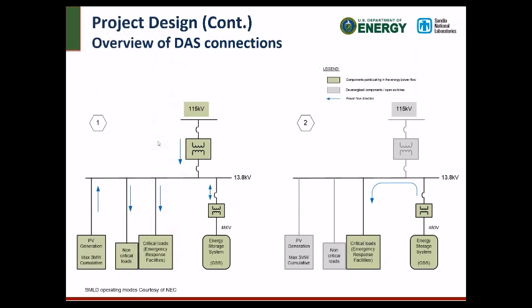So as you see on the screen now, on the left side we have a normally operating system. The green means it is on, and the arrows show the power flow. We have energy storage on the right and PV generation on the left, with critical loads and non-critical loads between. On the right side, if we had a utility outage, the battery is performing basically UPS backup to the critical loads.